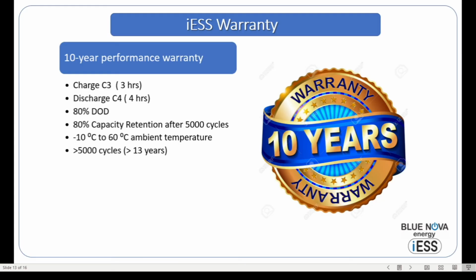Let's talk about the warranty. BlueNova offers a 10-year performance warranty with the iESS, which means that we warrant not only the workmanship, but also the capacity retention of the system and the performance of the system under typical 3-hour charge scenarios, discharging at 3 to 4 hours, down to 80% depth of discharge. We guarantee an 80% capacity retention after 5,000 cycles with operating environmental conditions of -10 to +60 degrees Celsius ambient temperature. And what we're saying is that for more than 5,000 cycles, which is basically more than 13 years, we have a performance warranty on the system.